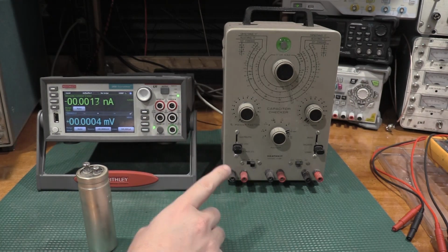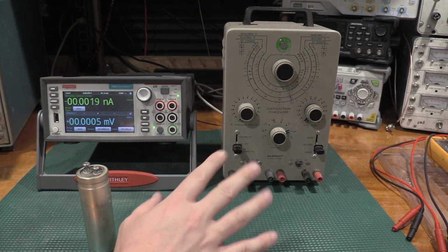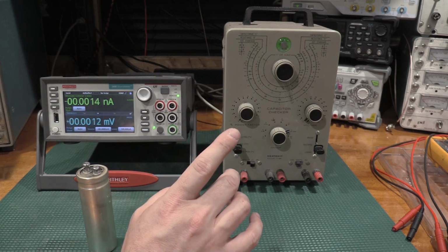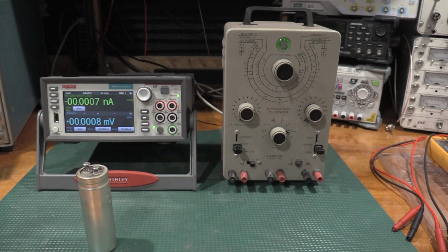This is not calibrated. I need to get some standards so I could actually calibrate the bridge. But the leakage is in good shape. However, there's a problem with it that I will demonstrate in this video, and it has to do with unregulated power supplies. Over here is a source measure unit. This is a more exotic piece of test gear.